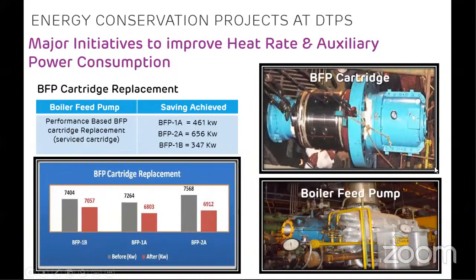And the next major initiative we used for reducing the aux power consumption was BFP cartridge replacement. Our boiler feed pump is an auxiliary which has a very high head, and it lifts water from 0 meter to roughly boiler top, which is the drum level. So it has a very low suction and delivers to a very high head. So the power consumption of this auxiliary is very high. It is the highest power consuming auxiliary in our plant. It roughly consumes 7,400 kilowatts of power and it is running 24 hours.